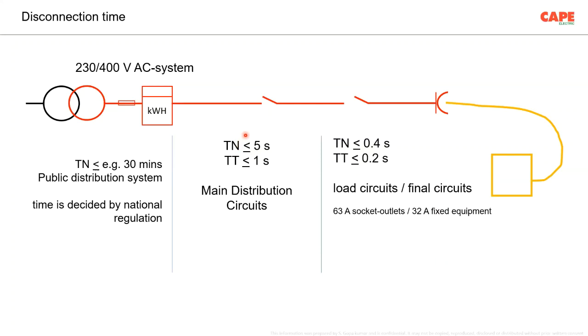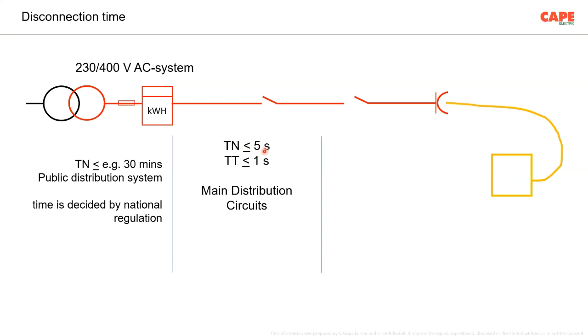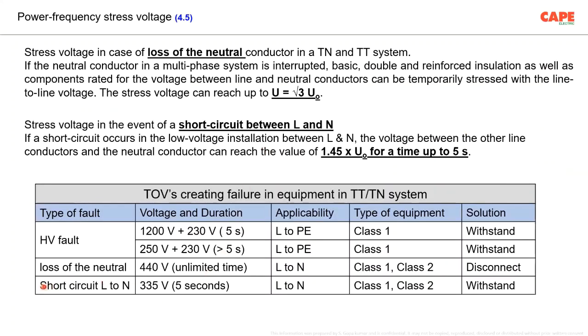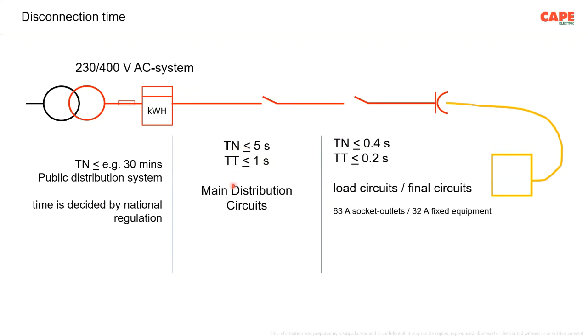Actually, the 5 seconds, for example, in a line to neutral short circuit, 335 volt, which is shown in the previous slide. Say here, line to neutral short circuit, 335 volt, 5 seconds, line to neutral, applicable for class 1 and class 2 equipment. It comes from the disconnection time of TN system, 5 seconds. But please be sure that this time in the main distribution circuit up to 5 seconds is recommended for the safety measure called protective equipotential bonding and automatic disconnection of supply.